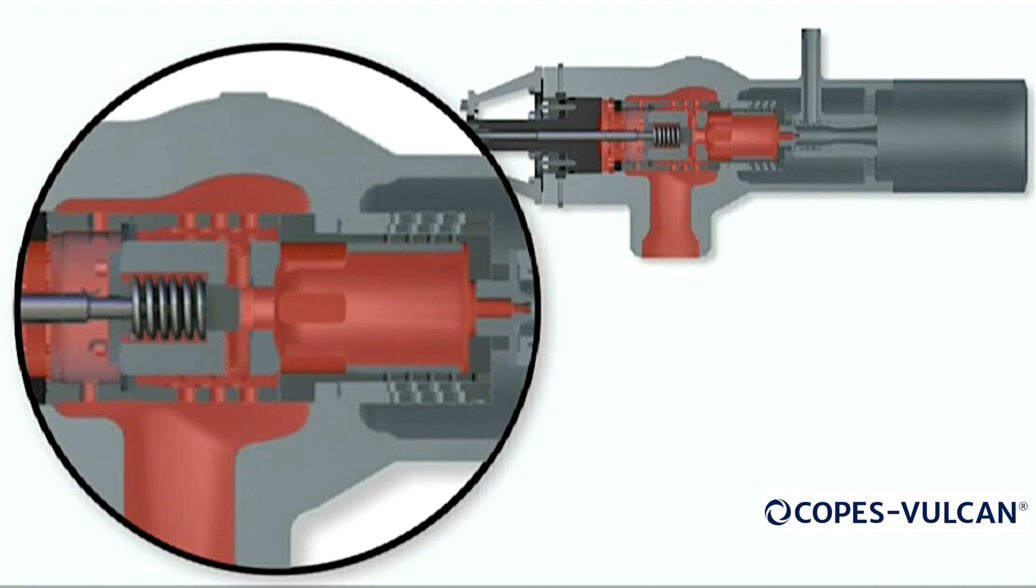The main plug is now balanced, reducing the actuation thrusts required. High pressure balancing, or P1 balancing, is a key design feature of the DSCVSA for reliable smooth operation.